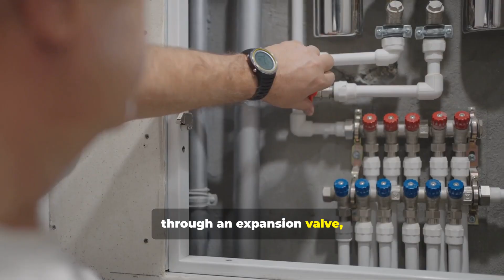The efficiency of this system is remarkable. For every 1 unit of electrical energy consumed by the compressor, the heat pump can deliver 3 to 5 units of thermal energy to the district heating network. This is because it is not creating heat, but simply moving and concentrating it. This makes the recovered heat from the data center an incredibly energy-efficient source for the city. It leverages a waste product, applies a small amount of high-grade electrical energy, and produces a large amount of valuable, high-grade heat. In Finland's cold climate, where heat is a valuable commodity for more than half the year, this technology turns the data center's biggest liability into one of its most important assets.